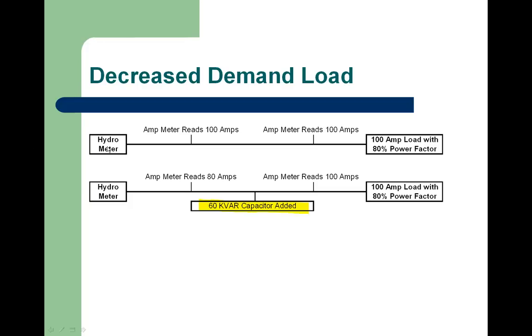The hydro meter would be registering 100 kVA, and as it's alternating current, it registers it 60 times a second, back and forth. So if you were to look at a hydro bill at this particular site, the kVA demand would be 100, and the kilowatts would actually be 80.